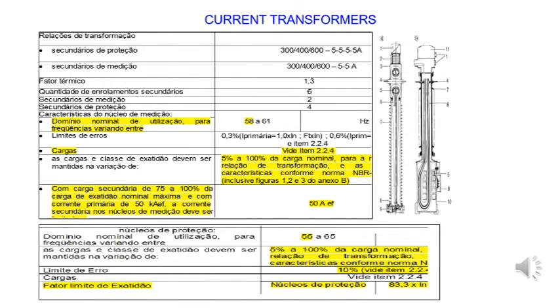For current transformers, we will not go into details, but basically the specifications related to the passage of currents and to the application of overvoltage are more or less the same as we saw before for the isolators, disconnectors, and so on. The only thing which is interesting to mention for current transformers is that there are some tests which are applicable to the protection cores and to the measuring cores related to the passage of short-circuit currents.